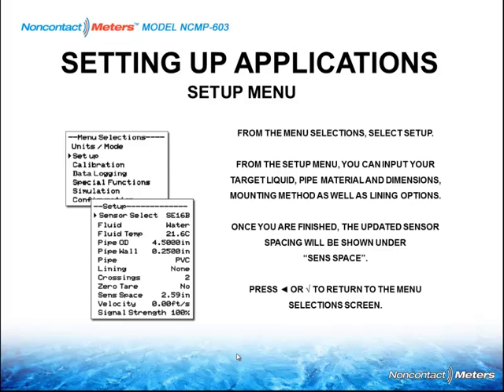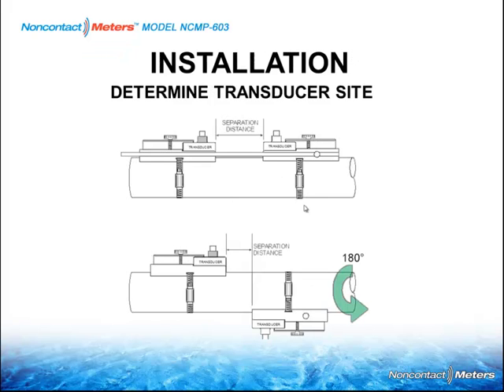The zero tare is zeroing the meter, don't touch. No need to re-zero your flow meter for your basic applications. Just stay away from that. Then it'll spit out your sensor spacing. So for this particular application, we have a sensor spacing of 2.59. And it also has some signal strength rating. So in this case, the sensor spacing at 2.59 is the differential from here to here, which is, notice, here's your nice mounting clamp. It's just like a stirrup. The sensor's under this big alligator clip here, and the back side of the transducer and the clip are the same. So this is your differential that you'd have for that particular application.